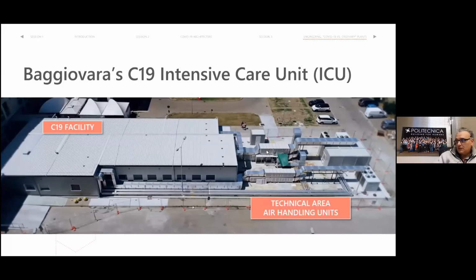One thing that I would like to say is, it has been asked of us to provide a system that can be reversible in the future, moving from an intensive care unit for COVID-19, which is under negative pressure because they are infectious patients, to an intensive care unit for normal use, which is generally over-pressurized because they have immune suppressed people, or let's say weak people inside. So this is absolutely possible because, just adjusting the speed of the fans, we can change the pressure inside. So we can increase the supply and reduce the return, and we increase the pressure inside. The opposite to decrease the pressure inside.